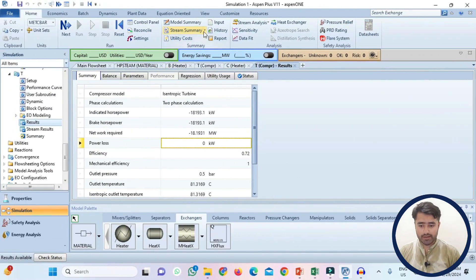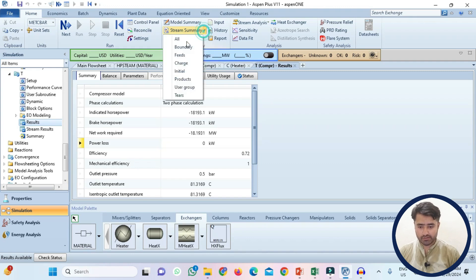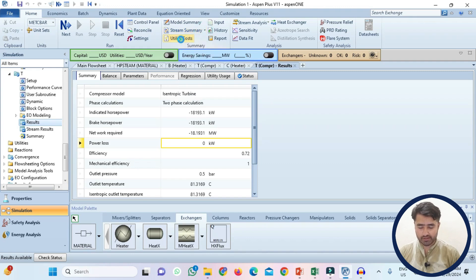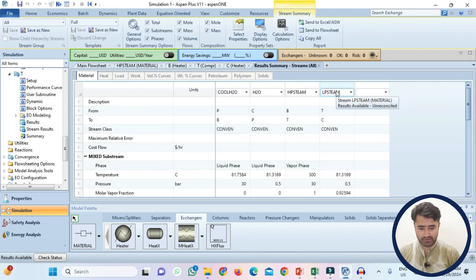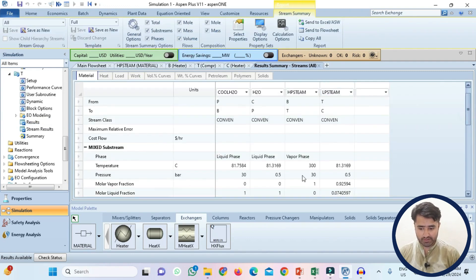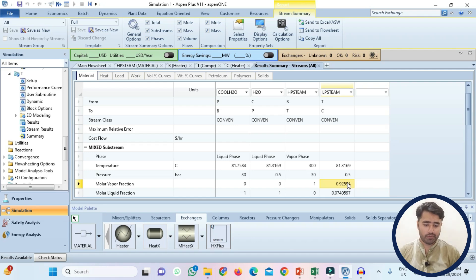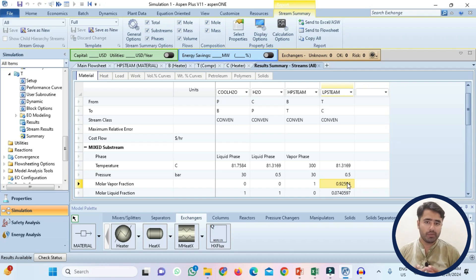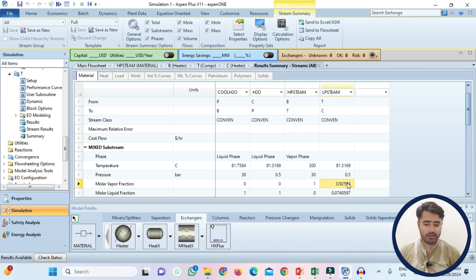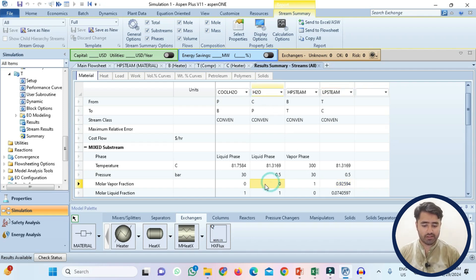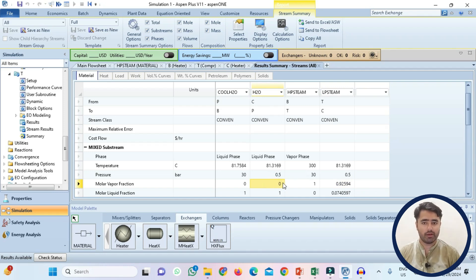Now I will show you the stream results. So in the stream results, if you check the low pressure stream here you can see that vapor fraction is 92%. It means that after the turbine the steam will be in the two phase region, 92% will be vapor while 8% will be in liquid phase. Then after condenser all of the steam is converted into the liquid. So that's why here the vapor fraction becomes zero.